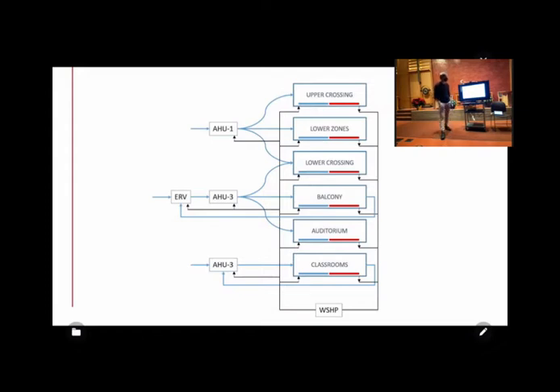of the building. And one of the things that I will mention that was a big point of contention in the design phase was that we didn't think that this water source heat pump, which I think has three different operating capacities, was a good idea. Essentially, we were saying that under really low load circumstances, that thing is going to want to turn on and then turn right back off, because radiant floors aren't dumping enough energy under low load circumstances.